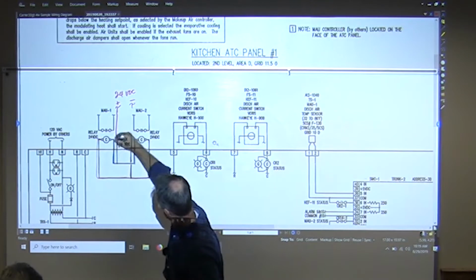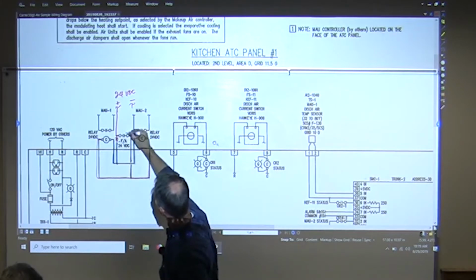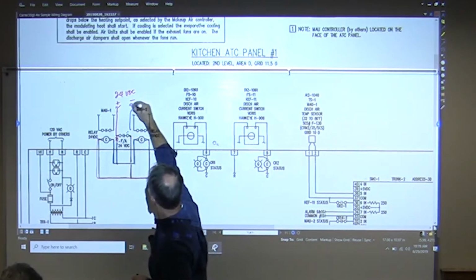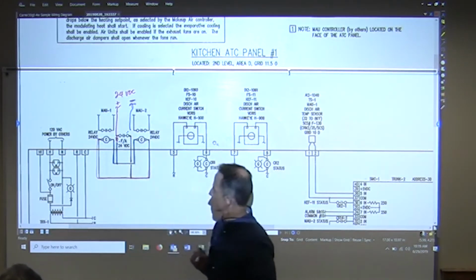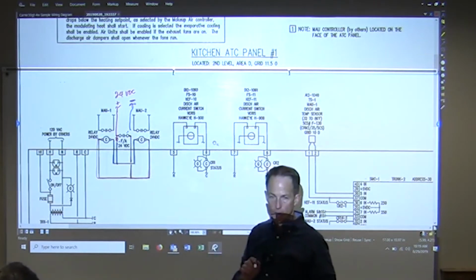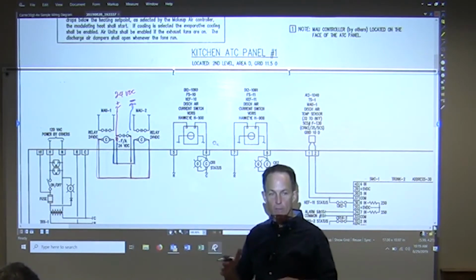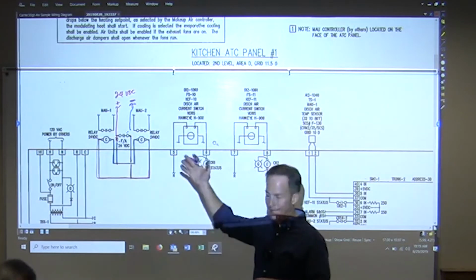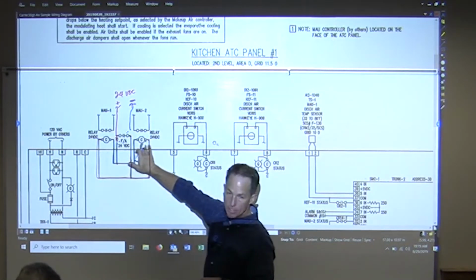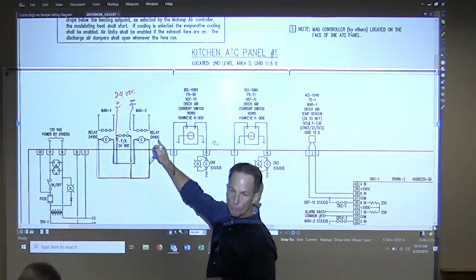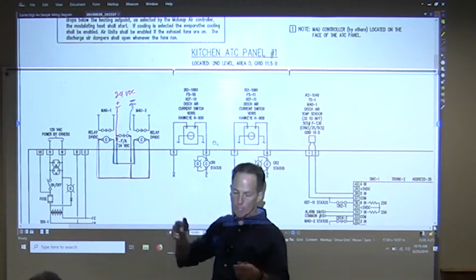Bring that back to the common source of the 24 volt. So this is coming up, and then somehow, and I'm going to just do a dotted line to get over here so we can get to the minus. Okay? So that's how we fix that using the existing equipment. I've got a DC relay because it's saying that's what it is. So I didn't have to change any equipment.